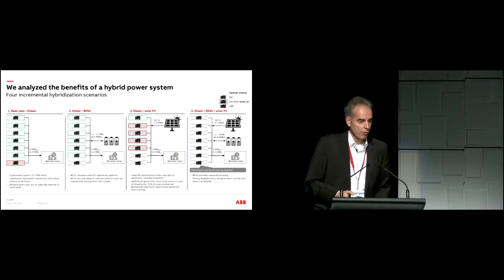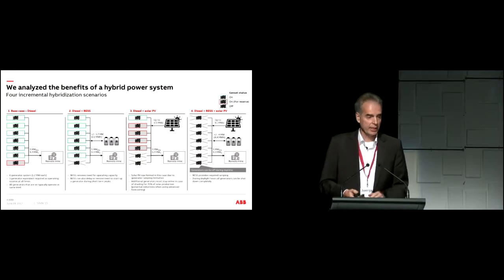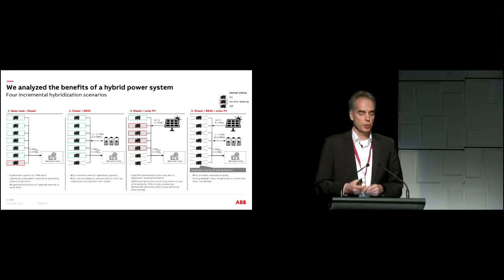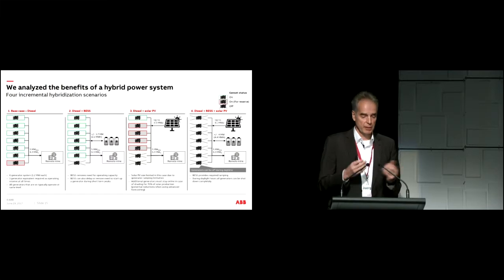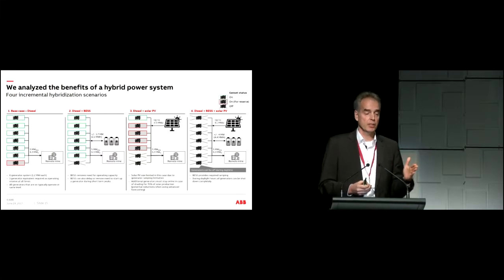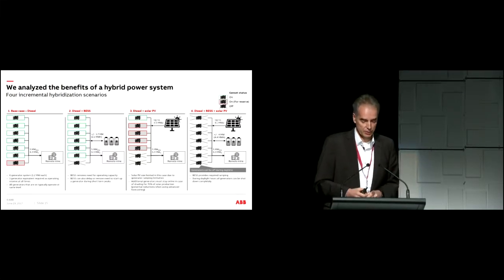So we ran four different business cases. Starting on the left, business as usual: the diesel power station. We're running up to six generators supplying the load, but one generator is always kept online for spinning reserve, in case one generator drops offline, so the others can pick it up without causing a blackout. That's our reference for an NPV calculation, done over 10 years.